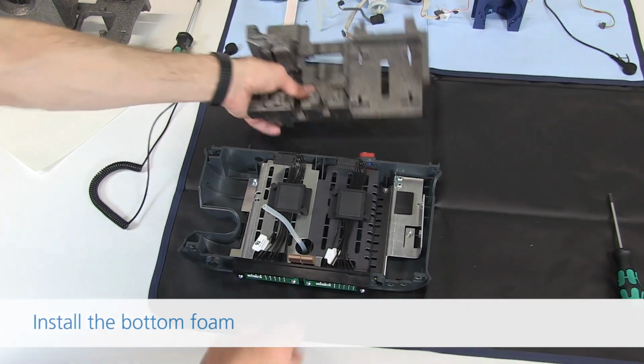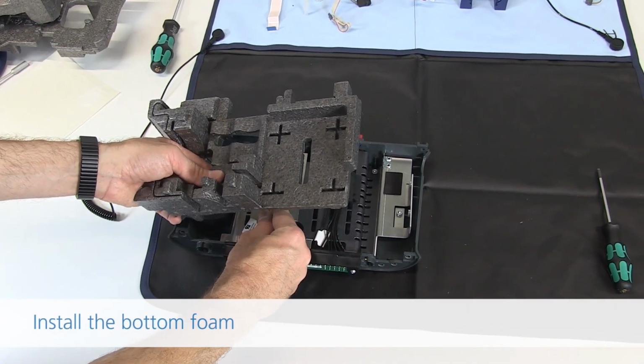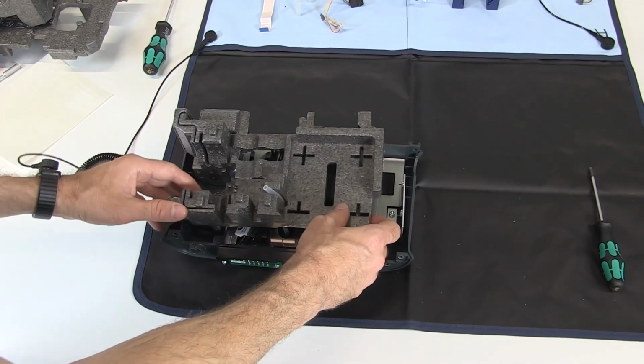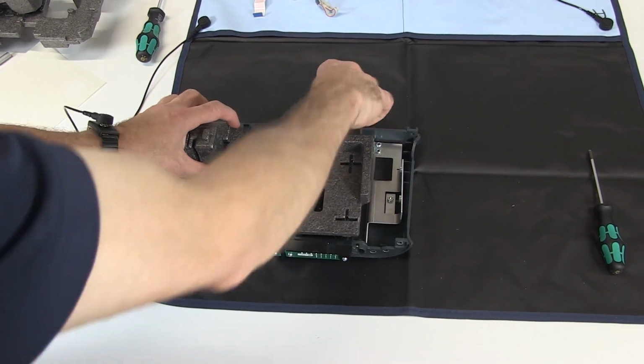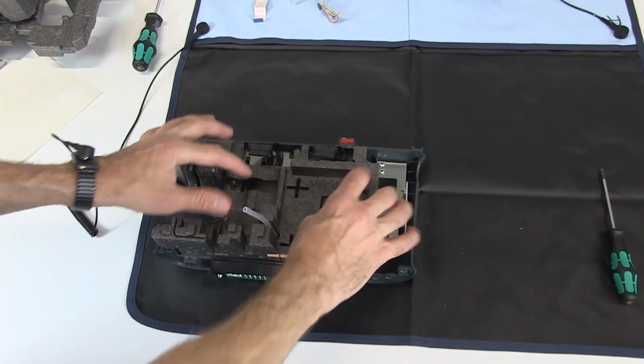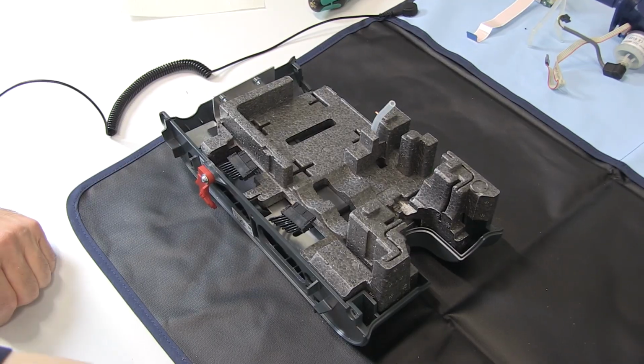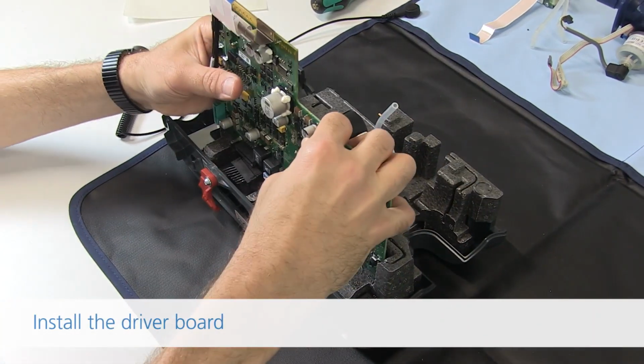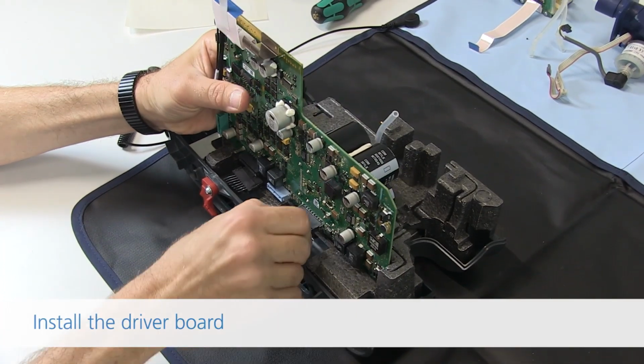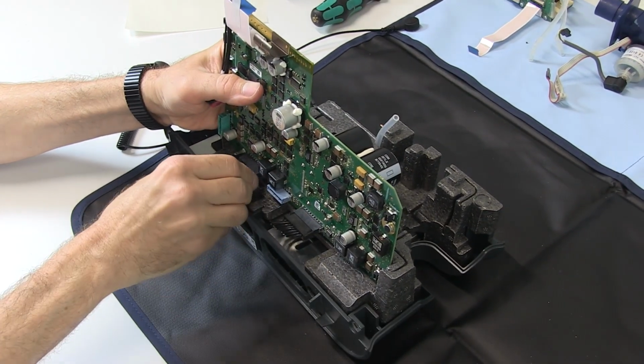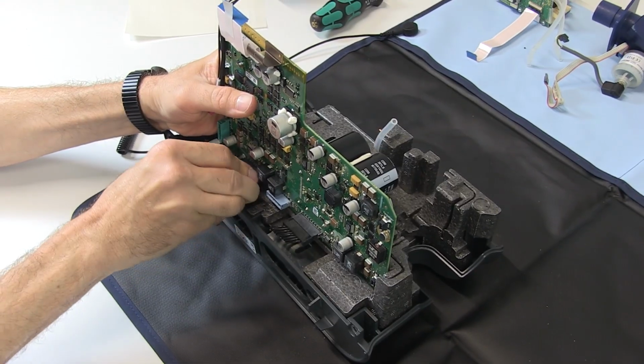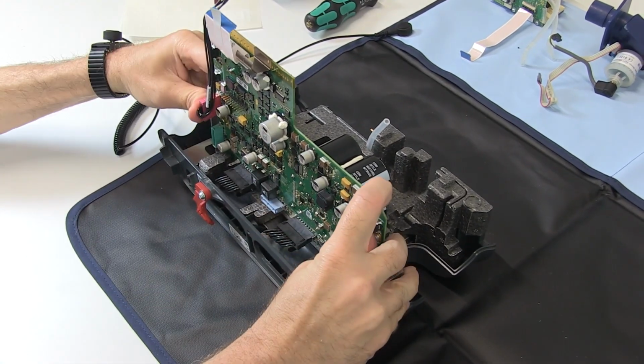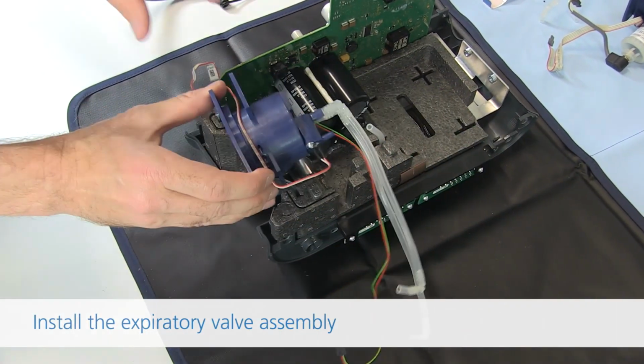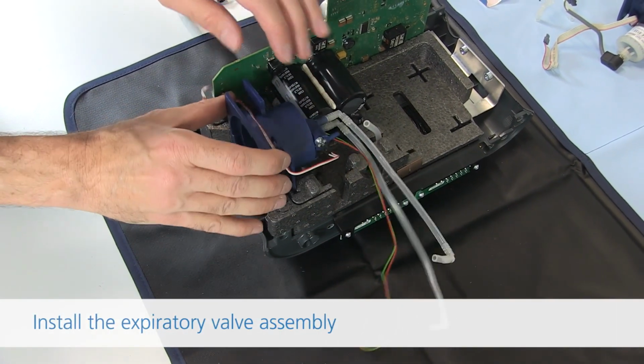Insert the tubing for the expiratory valve bleed port through the designated hole in the bottom foam, then position the bottom foam on the mounting plate. Position the driver board on the bottom foam, then connect the 2 battery connectors to the driver board. Install the expiratory valve assembly in the bottom foam.